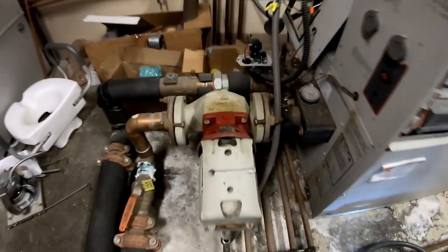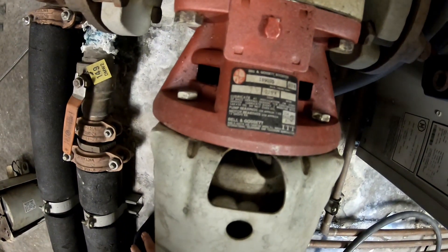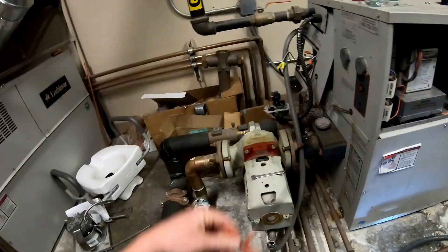What's going on everybody, Grim Repair here. Today we're going to be changing the motor out on this circulating pump that goes to our Lochinvar boiler - it's a Bell and Gossett. If this video helps you out, be sure to subscribe. Turn the power off to the unit. You're going to need a 1/8 allen key and a half-inch wrench.